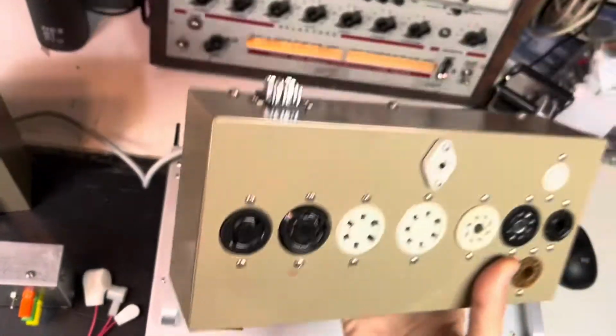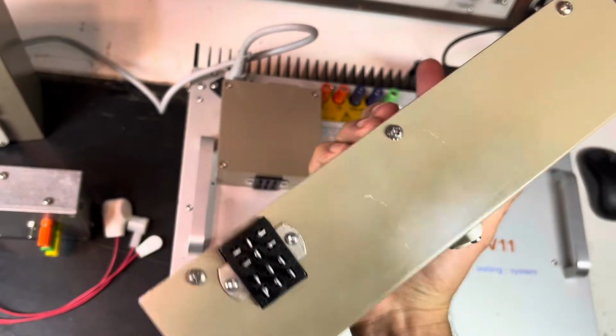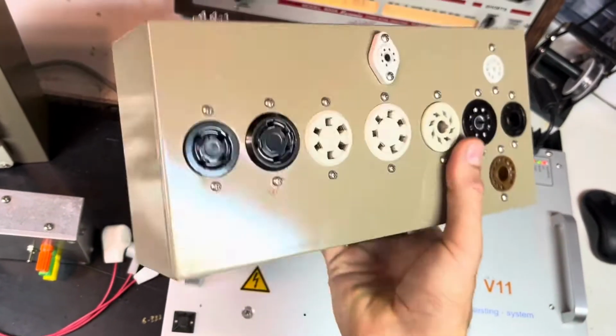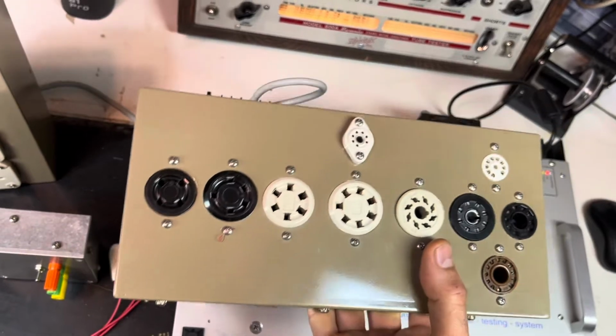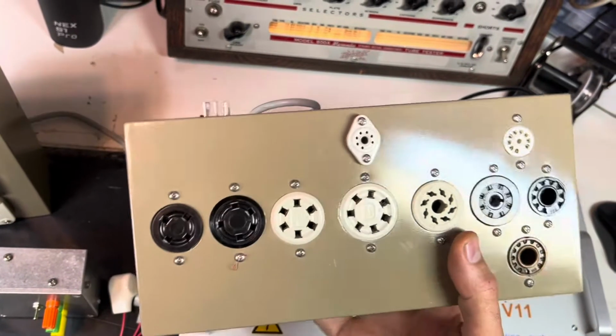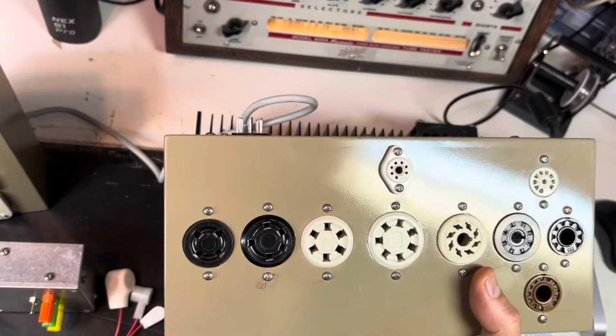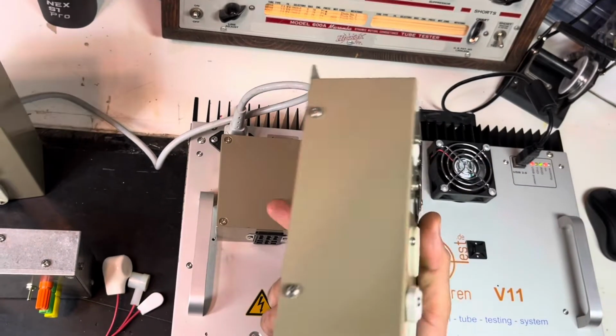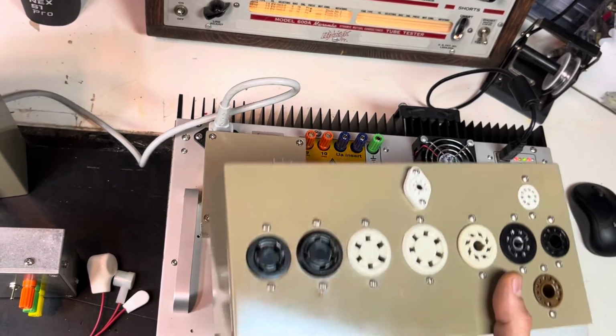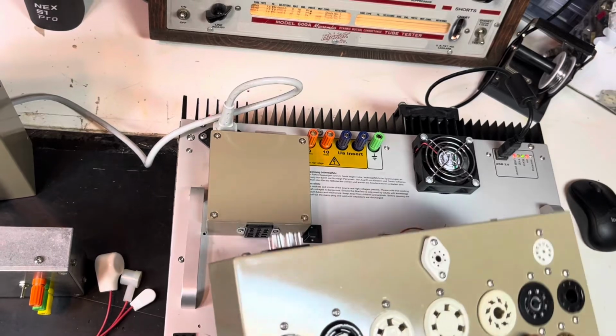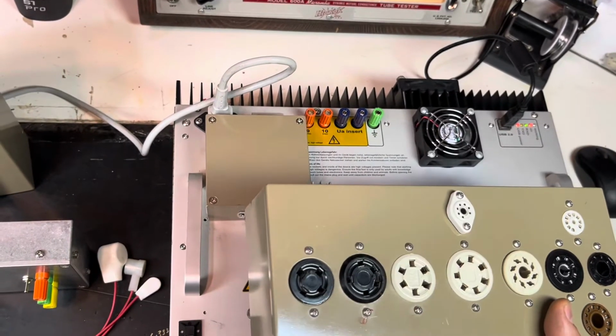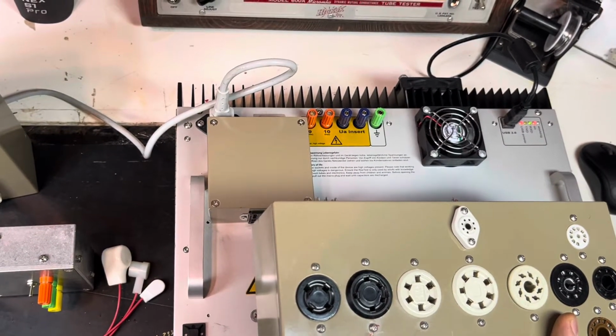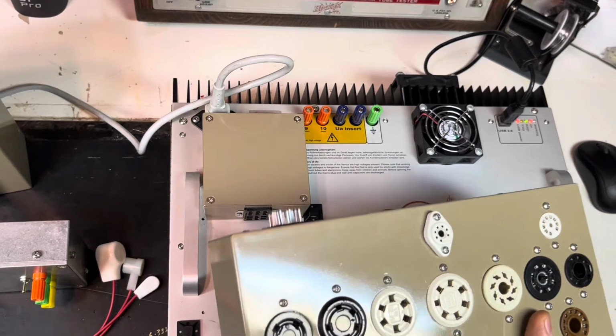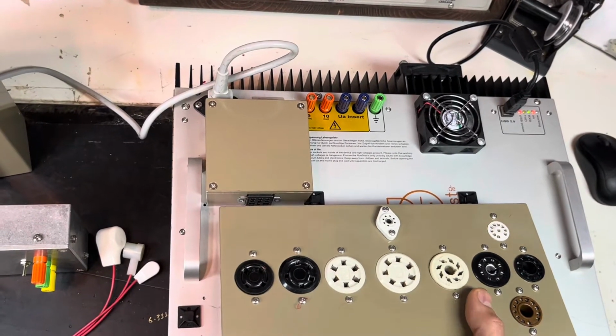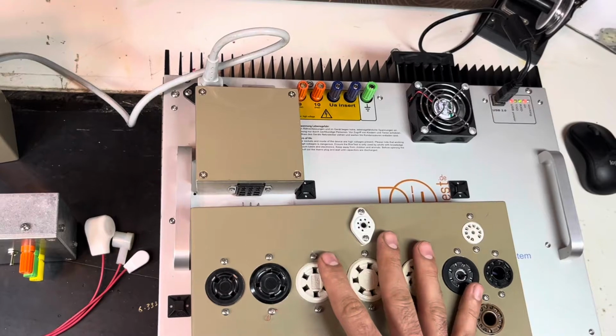So the socket box is really nice. It's all steel. It's completely shielded. All the wiring is extremely low resistance, thick wiring, so there are no losses. Keep in mind, this has to be kept very short from the PC board under the chassis, because even milliohms of resistance during the calibration compensation matters. So that's why he suggests that you keep it short.